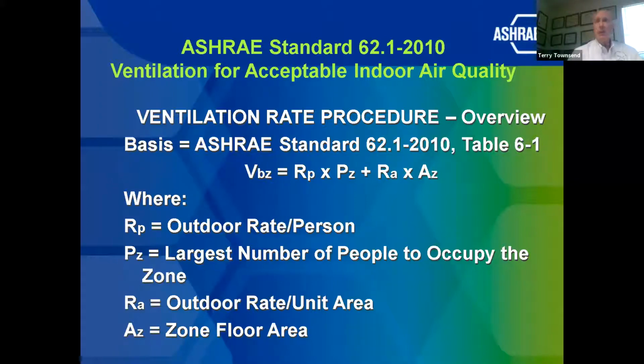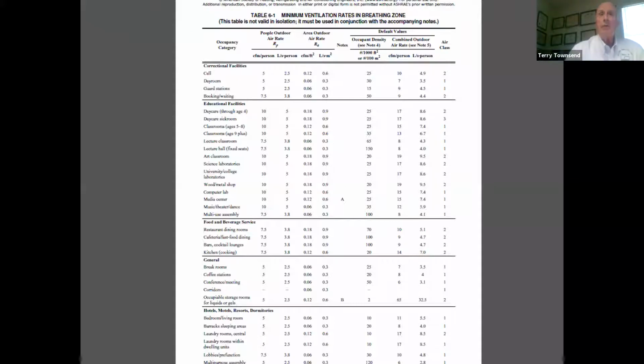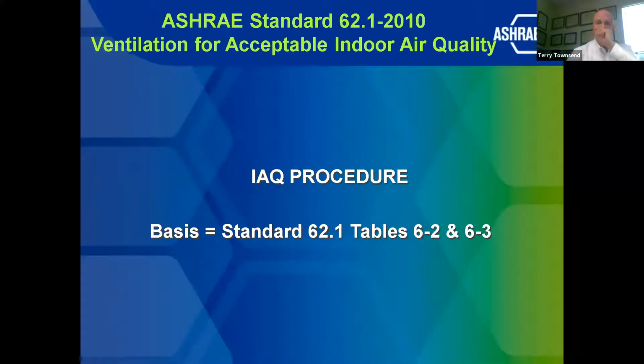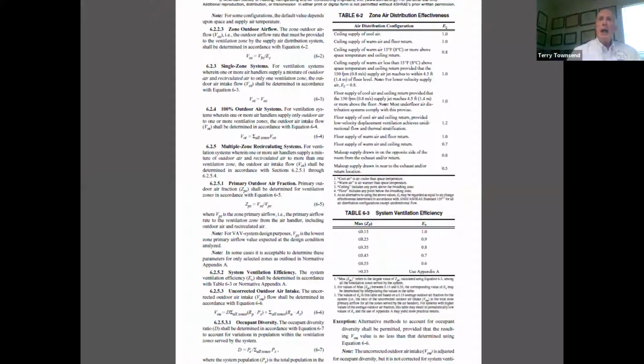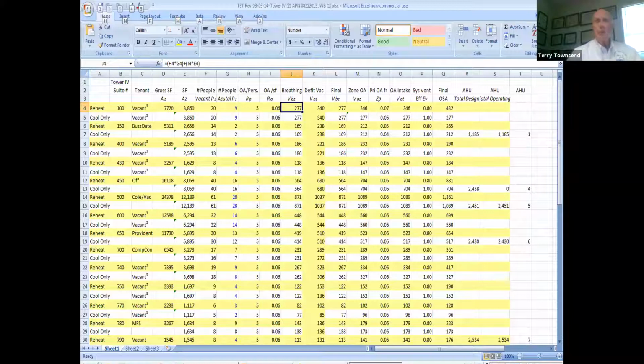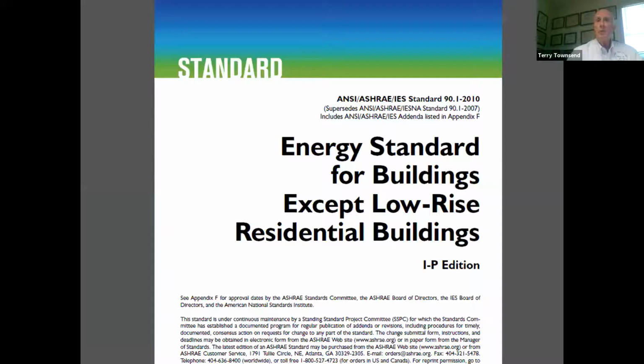Now, if we look at the ventilation rate procedure in Standard 62, Table 6-1, hopefully you're familiar with this equation, which gives the rate per person as well as the outdoor rate per unit area, and you utilize Table 6.1 to get the factors to integrate into it. For anybody that's not familiar, in the appendix there are sample calculations utilizing information from this table. If we look at the IAQ procedure, this utilizes Tables 6.2 and 6.3. This information goes into the room air or zone air distribution effectiveness, as well as the efficiency of the ventilation system. Typically, you have to develop a spreadsheet for the different areas, for the number of people, outside air, and breathing area, and then come up with the effective ventilation rate.